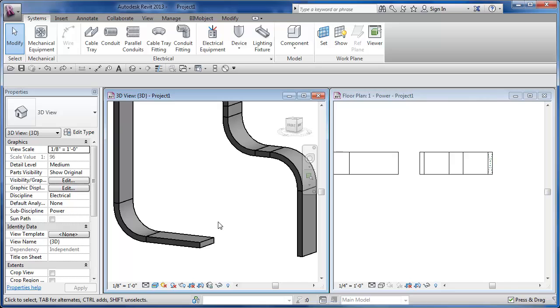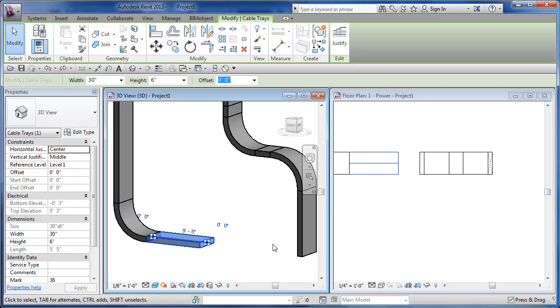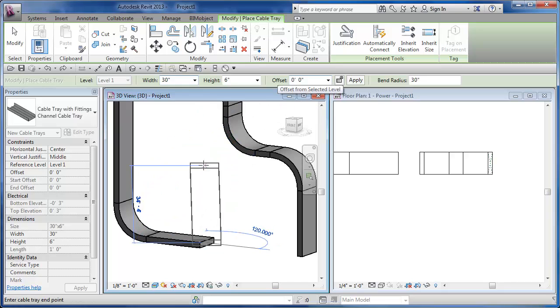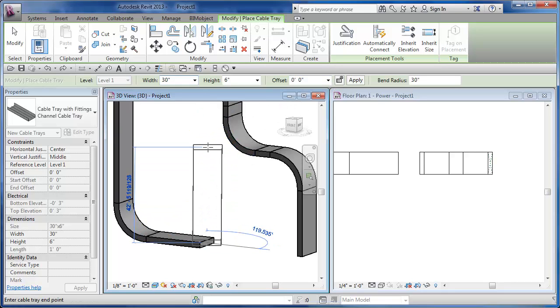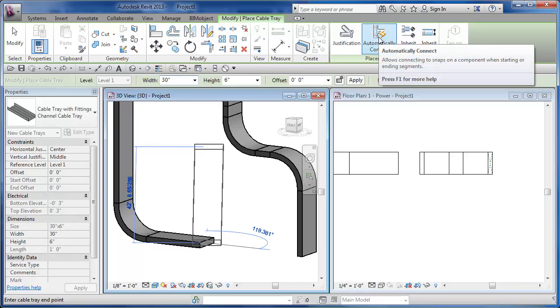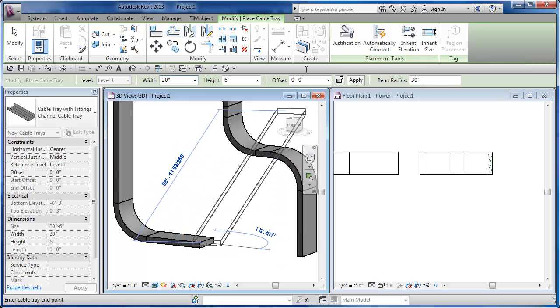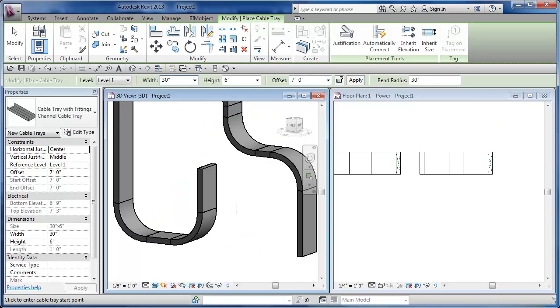That didn't work so well — you can see there was a section rotating, with the cable tray coming up vertically, which is kind of typical. So we'll work through it. We'll pick on here; the best way is always to right-click and say 'Draw Cable Tray'. It looks like it's not coming off straight, so I'll turn off 'Automatically Connect' so it doesn't touch anything. I'll go back, set seven feet again, make sure to hit Enter and then Apply — that works a bit better.